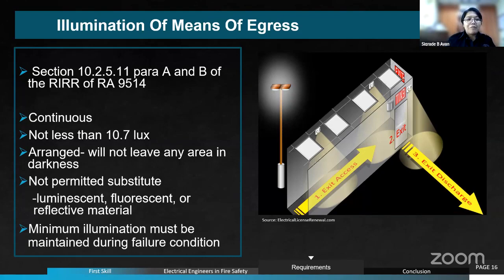That's why ang requirement ng Fire Code is that our illumination will be not less than 10.7 lux. It should be arranged na lahat ng area natin ay well lit, walang dapat darkness. At the same time, hindi natin inaallow ang luminescent, fluorescent, or reflective material as substitute for the illumination of means of egress. And the minimum illumination must be maintained during failure condition.